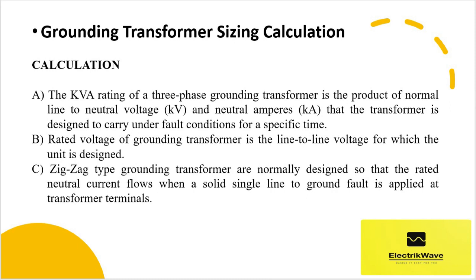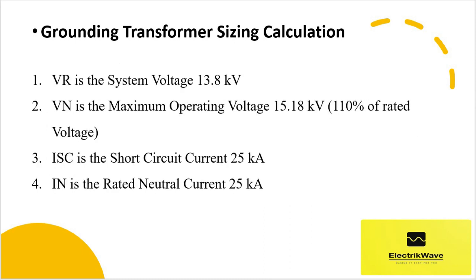Here, Vr is the system voltage: 13.8 kV; Vn is the maximum operating voltage: 15.18 kV (110% of rated voltage); Isc is the short circuit current: 25 kilo-amperes; and In is the rated neutral current: 25 kilo-amperes.